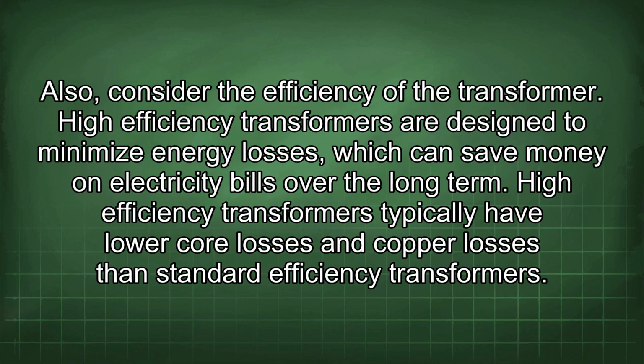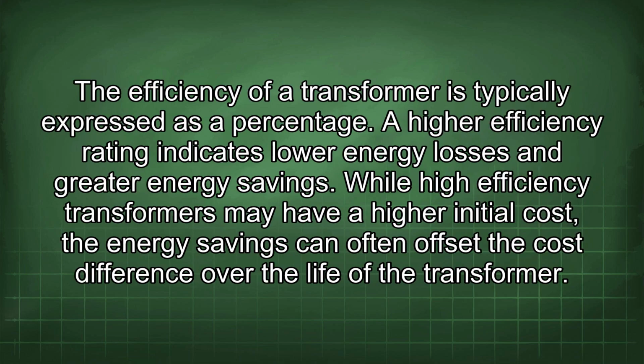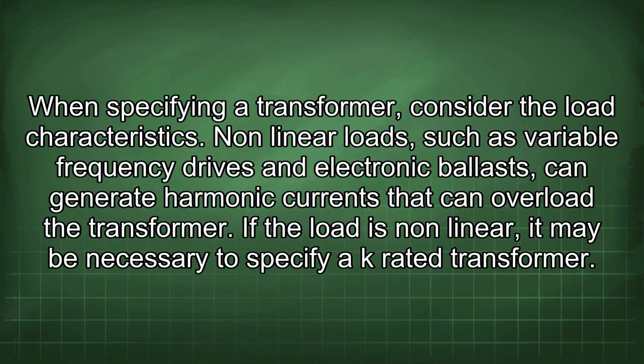Also, consider the efficiency of the transformer. High-efficiency transformers are designed to minimize energy losses, which can save money on electricity bills over the long term. High-efficiency transformers typically have lower core losses and copper losses than standard efficiency transformers. The efficiency of a transformer is typically expressed as a percentage. A higher efficiency rating indicates lower energy losses and greater energy savings. While high-efficiency transformers may have a higher initial cost, the energy savings can often offset the cost difference over the life of the transformer.